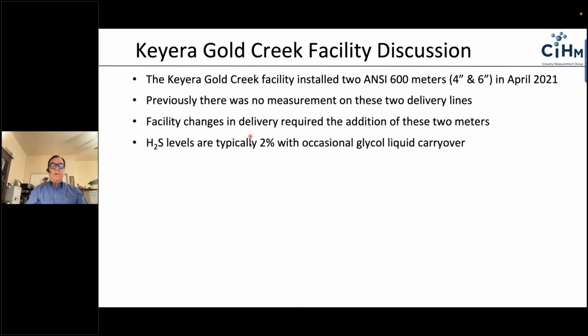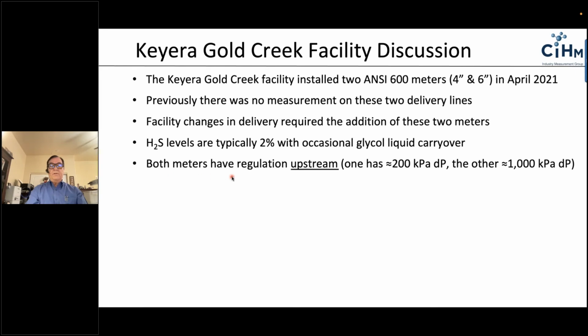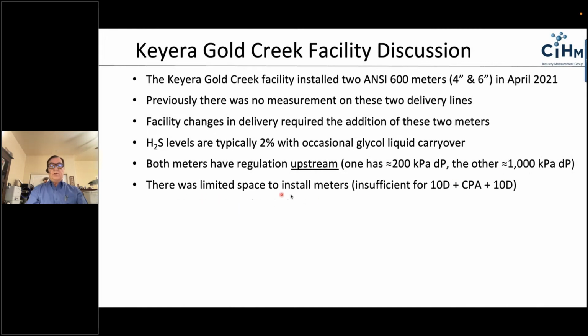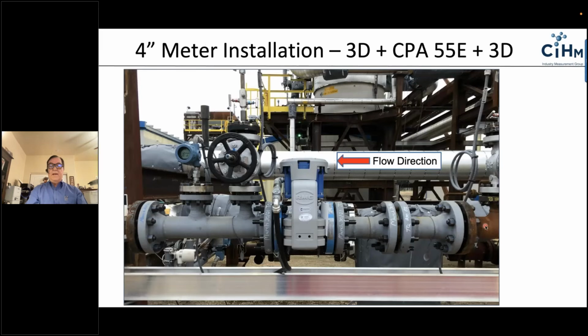H2S levels can typically be around 2%, and an occasional glycol carryover will be going through the meter. Both meters have regulation upstream, which isn't ideal, but it is the way it is. One of them had around 200 kPa of differential, the other had about 1,000 kPa of differential upstream of the meter. Space was also limited for a full installation of a 10D, CPA, 55E, 10D, so we'll be showing you what we used for that installation. Metering pressure is typically around 7,400 kPa for both line sizes. In the photo you see here, the flow is from right to left. You can see we used a 3D spool here, CPA flow conditioner, and 3D.